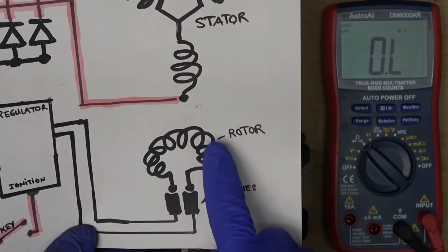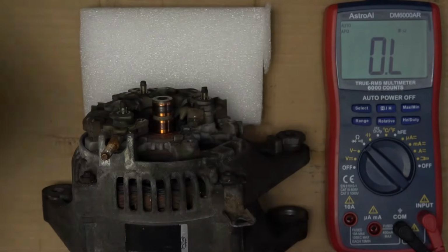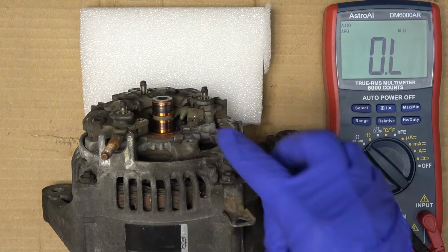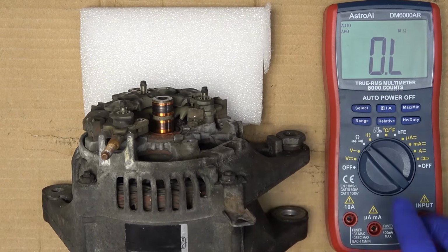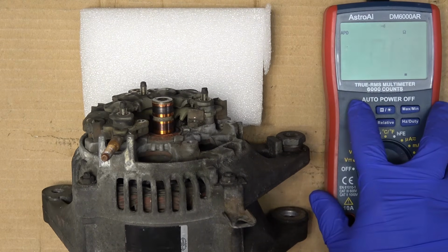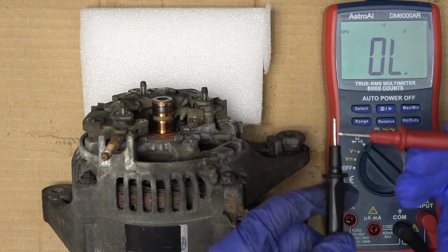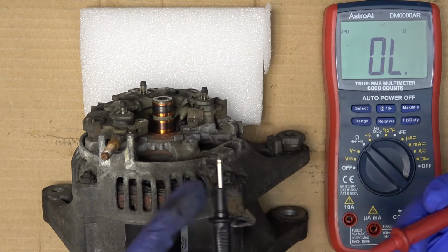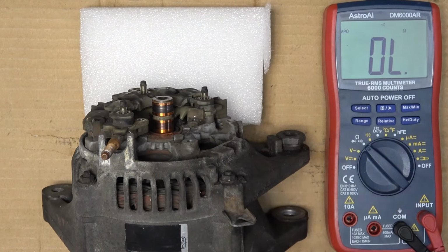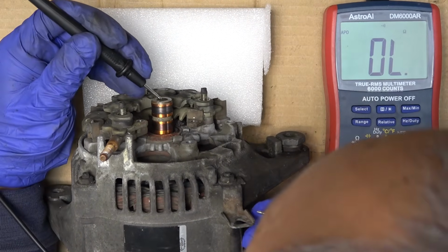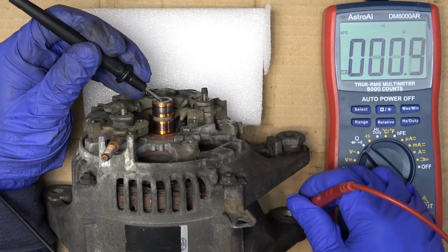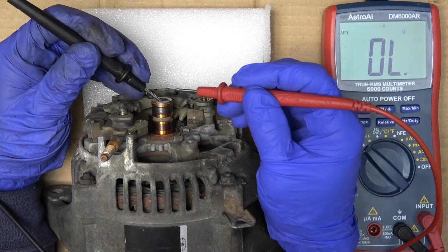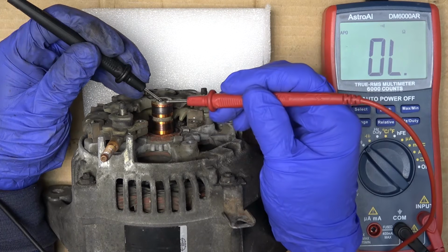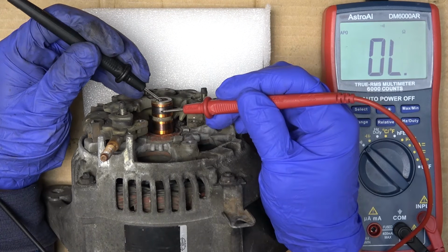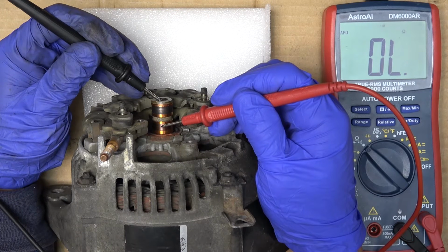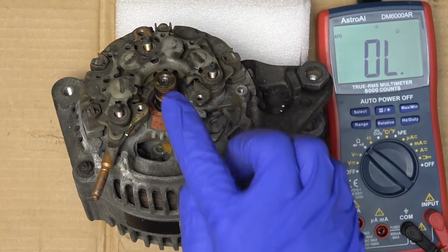The rotor winding is free floating, it's not connected to ground. So I want to make sure it's not shorted to the body of the alternator. I'll put it on continuity test, so when this touches, it will beep. The center of the shaft is ground, so I want to make sure it's connected to ground, and that the winding is not connected to ground. That's not connected, and that's not connected. So the rotor has normal value and works fine.